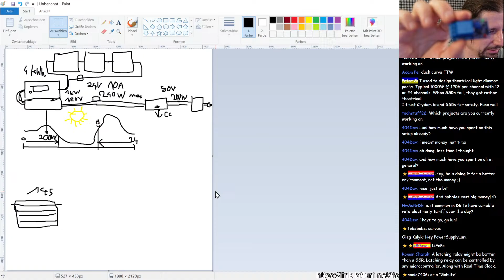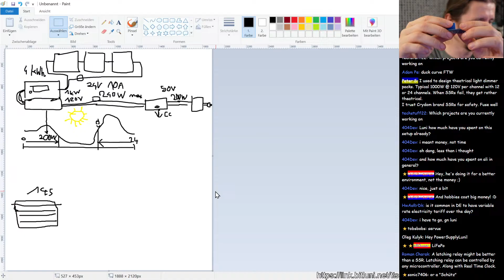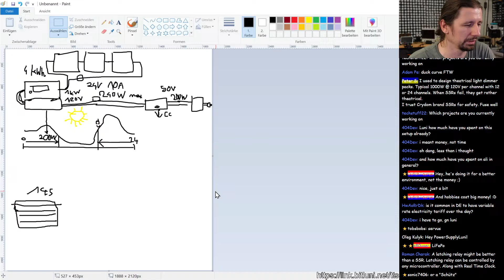If you use one of those, they degrade quite quickly because you get sparks, and they will melt and probably even weld - the contacts would weld and it won't open or close anymore, or open in that case.